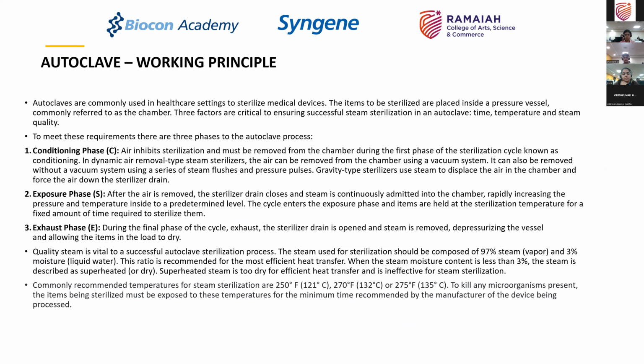The working principle of an autoclave, used in a healthcare setting to sterilize medical devices, is also used for component preparation in the industry. The sterilized items are placed inside the pressure vessel. The time, temperature, and steam quality are the three important factors which contribute to it. Of course, we are going to talk about all the factors which affect the autoclave in the subsequent slides, but I'm going to quickly rush through them because we have already been through that.